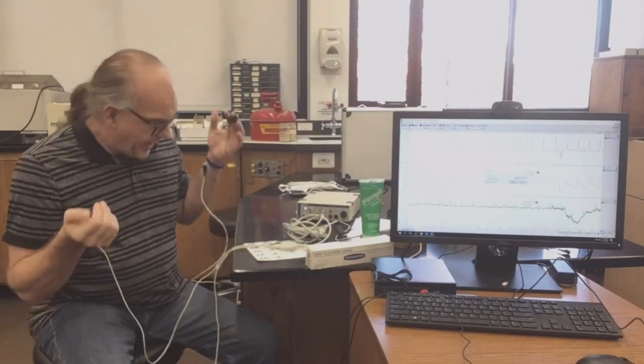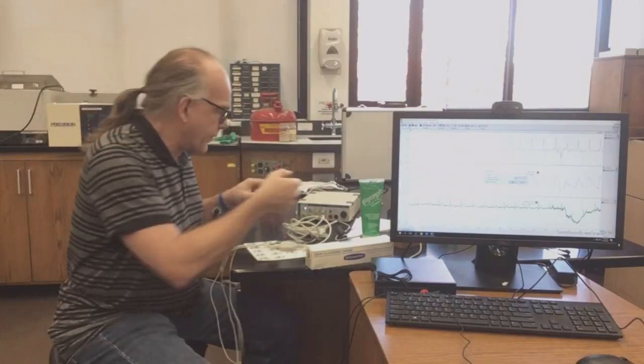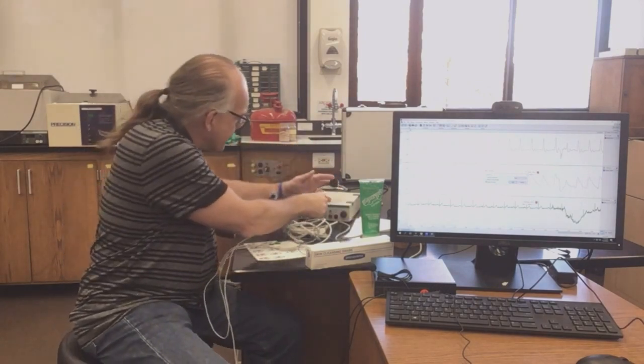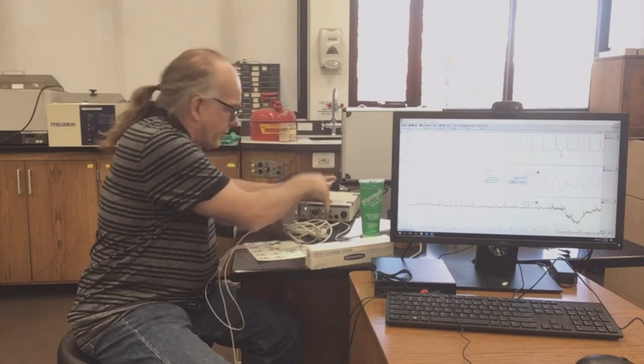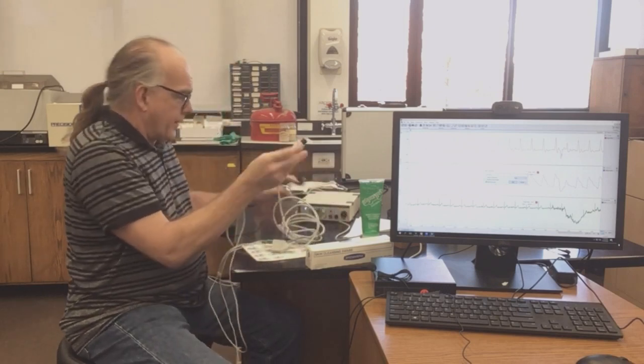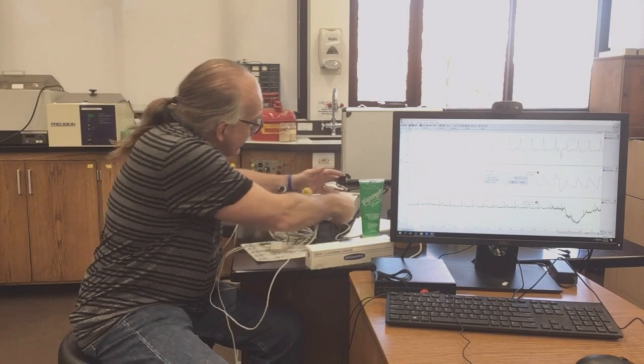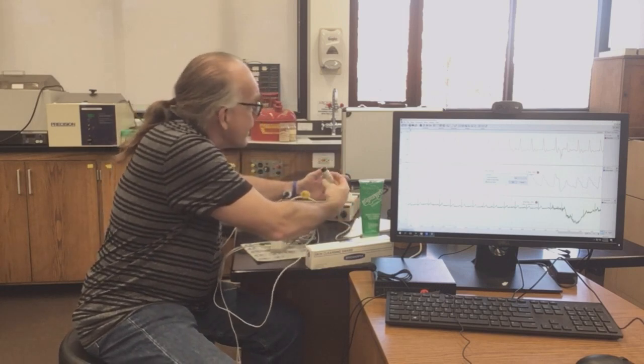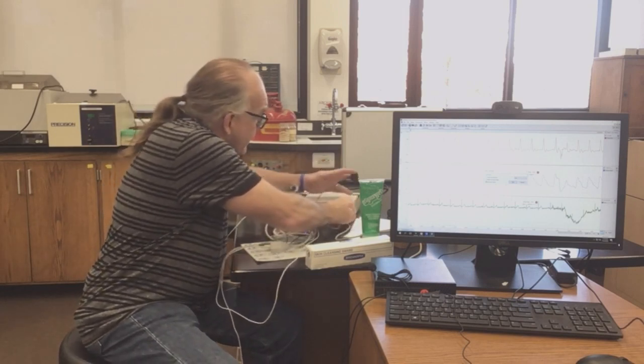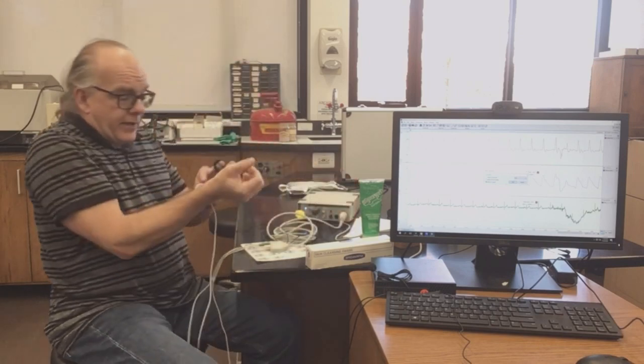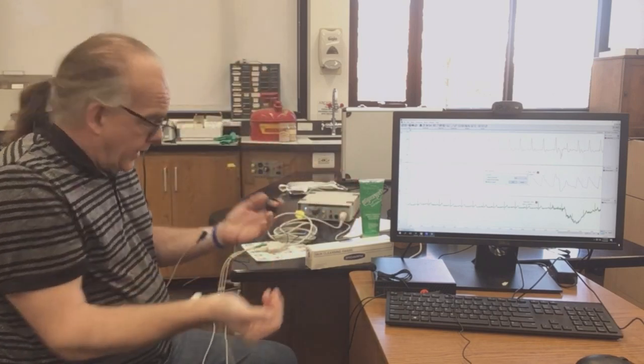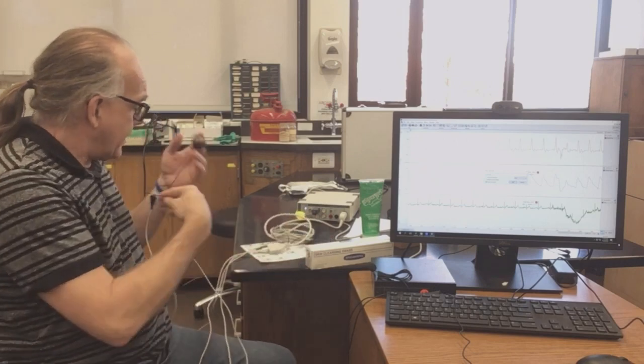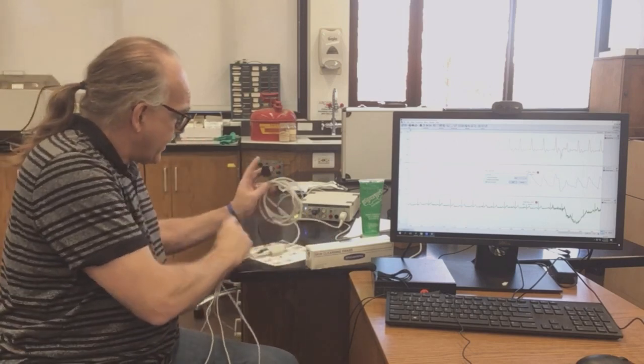Okay, so I'm back from running up and down the stairs for 2 minutes. We want to reconnect up the cables. So the pulse transducer going into input number 1, the 5-lead shielded cable will go into the bioamp connector. Again, it's only going to go in one way. Once we got everything there, double check and make sure the leads are still in position and that your test subject can get into kind of a relaxed position like they were sitting before.